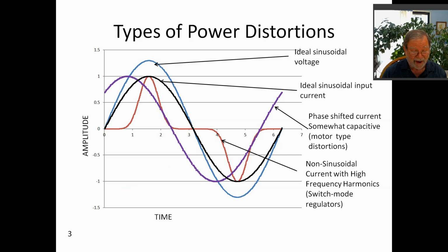This problem is usually caused by motors, but with the opposite phase shift. This is not our problem. The red line is a distorted load current form, which is usually the problem with switch mode regulators. This is the subject of the present discussion. It is the job of power factor correction to modify the current draw of the load circuit such that the distortions from the ideal are eliminated.